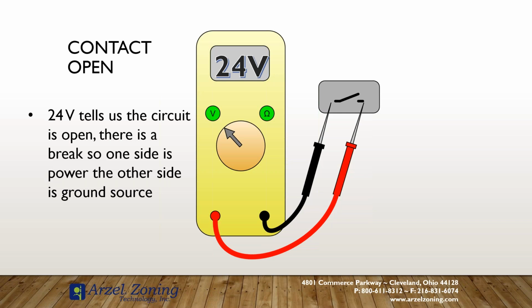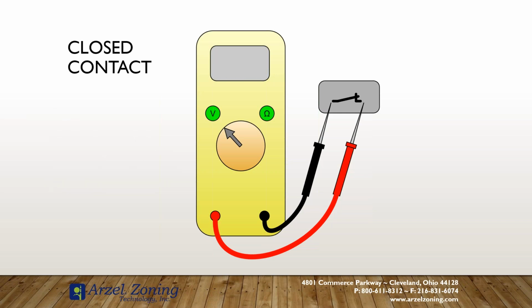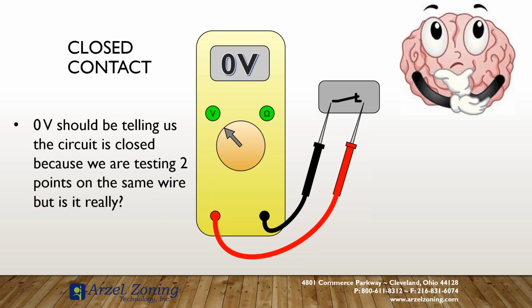Now, I want to be careful there because I also have to verify that I've actually got 24 volts to there. So if I read 0 volts, that doesn't necessarily mean that my switch is closed. I want to verify that I've actually got 24 volts going to that set of contacts. So the reason I like to use the resistance, which we talked about earlier, is because the resistance will tell me definitively whether or not that contact is closed. If I'm reading voltage, I need to test a couple different locations just to verify that there is actually voltage present. And if I can verify that there is voltage present, then a reading of 0 would tell me my contacts are closed, but a reading of 24 would tell me my contacts are open. So if my contact is open, I'm going to see 24. If it's closed, I'm going to read 0.